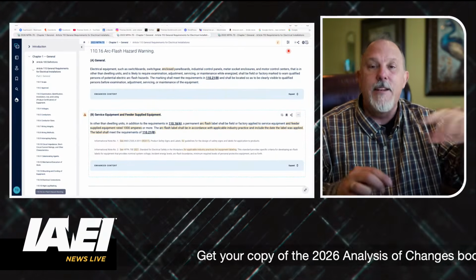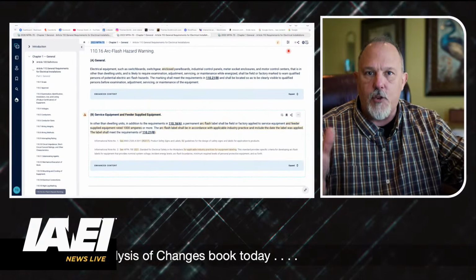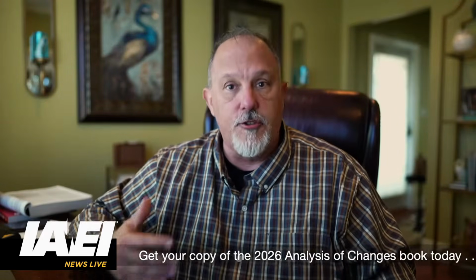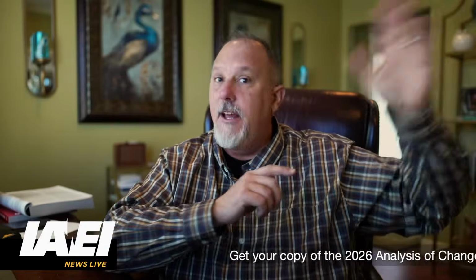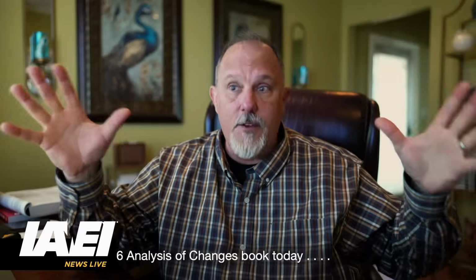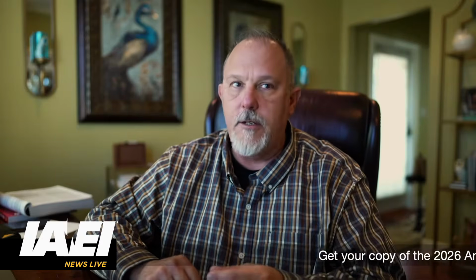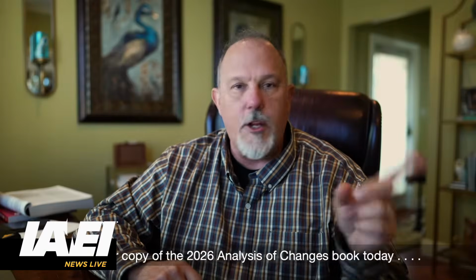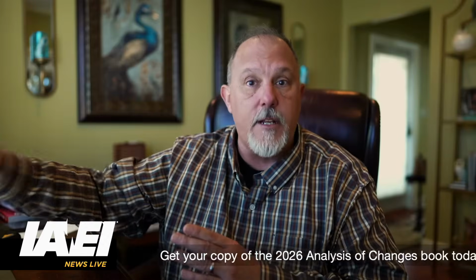for good reasons. We'll go into it. It was because if you use that list, if you're at service equipment and you use that list mistakenly for, say, a PPE category method, where you're going to determine your dress based upon those parameters, you are going to be underdressed for the application. It's service equipment. What's feeding it is what determines the incident energy. That's the line side. That's probably a fuse on the line side of the service transformer. If you're lucky. If you're not, you're in a secondary network where there is no transformer, but the clearing time is not there for arc reduction, and your incident energy at service equipment can be very high. So you wouldn't want to use that list of parameters to determine your dress. And we fixed that in the 2023 code, got rid of that list, and then said, hey, look, you need to specifically go to 70E, go to the right industry documents with a qualified person.